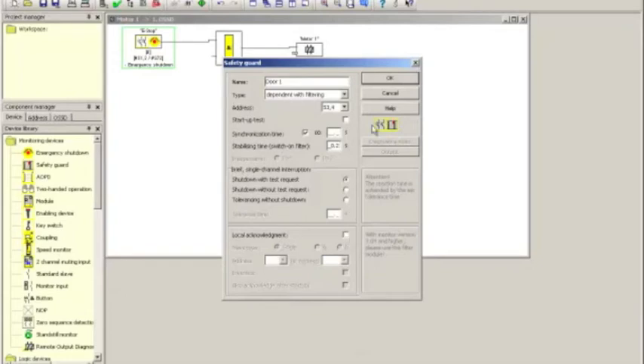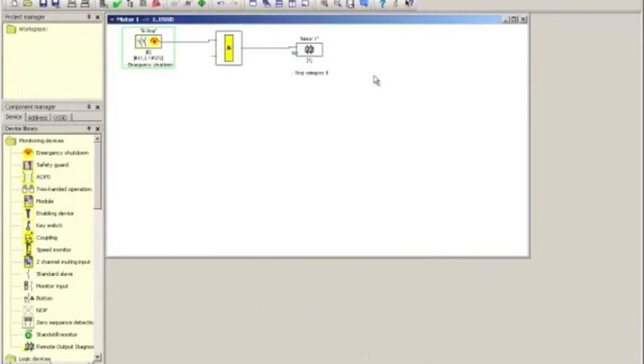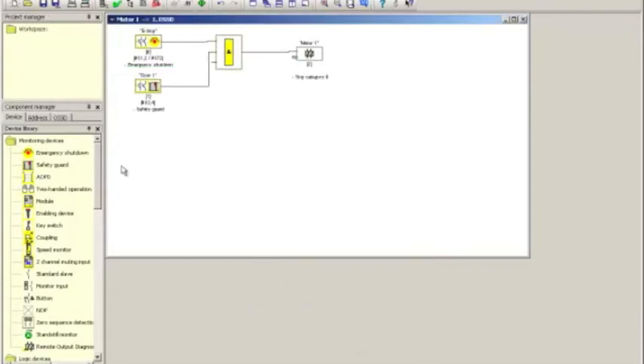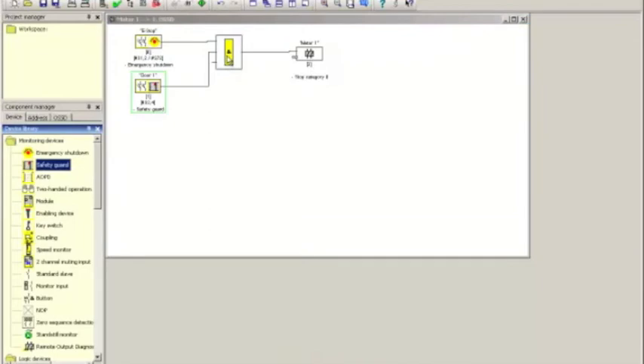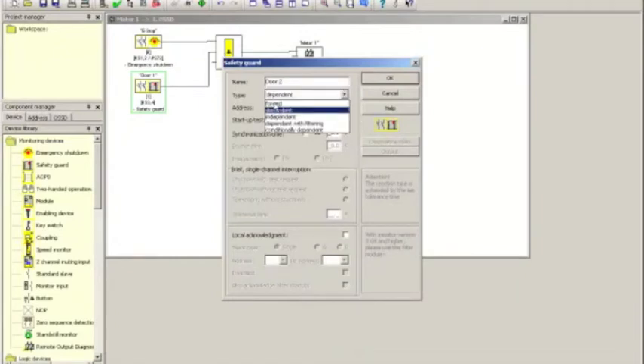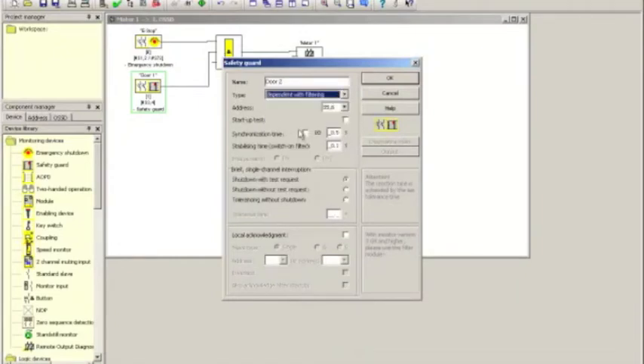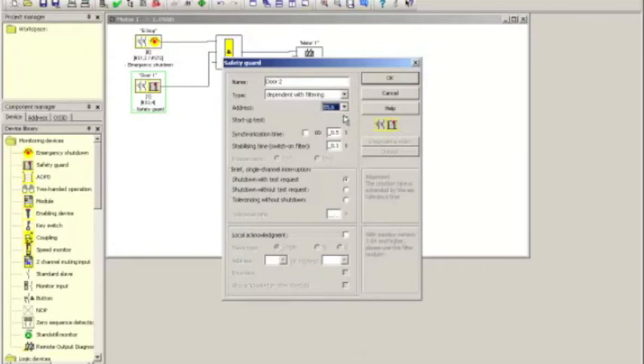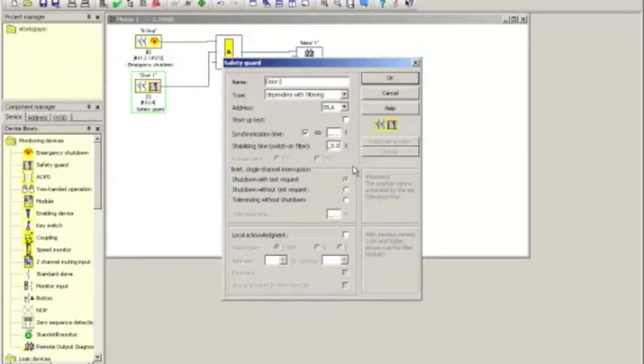Now, I click OK and go over and grab another safety guard. Call it door 2. Select dependent with filtering. There's really no more option in terms of the inputs because I've already used up two of the three that I had configured. I click on infinite synchronization time and I increase the stabilizing time to 0.2 seconds. Again, do not check local acknowledgement if you want this door to be auto-reset.